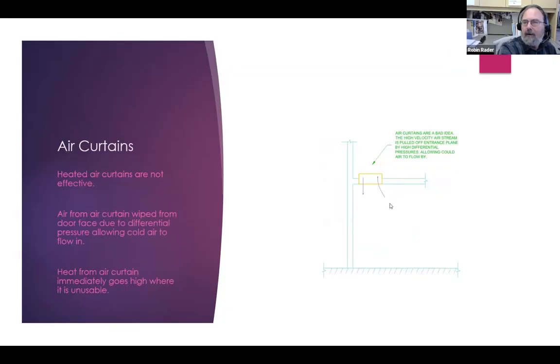So this is a picture of an air curtain. It's somewhat similar to that cabinet unit heater. Our experience in Fairbanks with air curtains is bad. Typically, the air pressure is negative enough that it pulls this stream off of the door and allows cold air to flow in. This hot air that is blown down essentially is turned up and goes to the ceiling, and so the occupants don't feel any effect of the hot air from this air curtain. So ASHRAE has now allowed single doors with an air curtain, and I'd be very careful with this. I certainly wouldn't use it where there's any occupants that are near the entry.